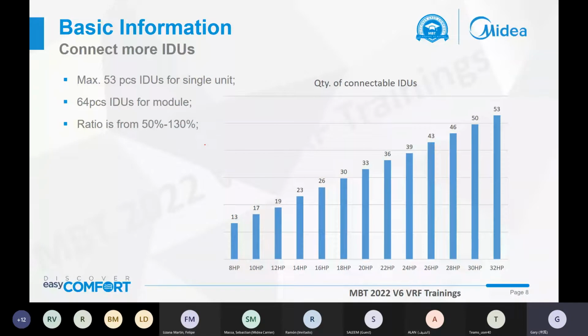Okay, the next part is for the connected indoor unit numbers. The bigger the capacity of the single unit, the more we have the maximum indoor units for the single unit. From 8 horsepower to 32 horsepower, we can see the maximum number of indoor units increases. For the minimum single VRF, we can connect 13 indoor units to one outdoor unit. For the bigger ones, we can connect 53 indoor units to one outdoor unit.